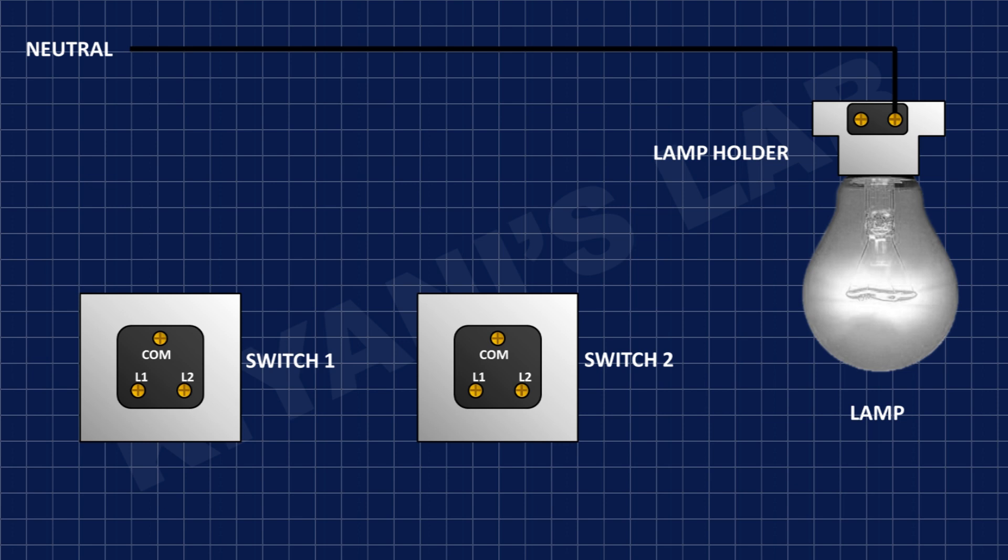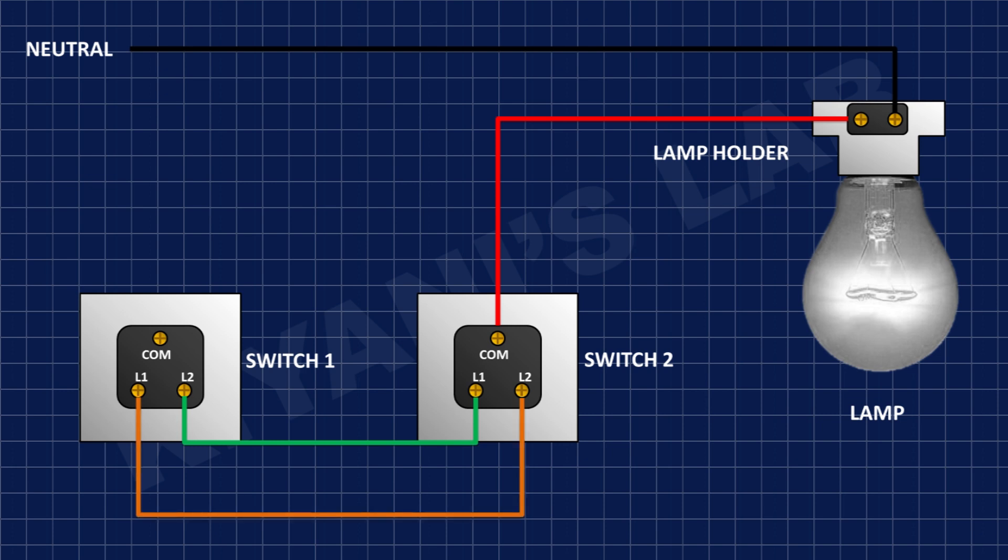After that connect the second wire of lamp holder to common pin of switch 2. After that connect L1 pin of switch 2 to L2 pin of switch 1. After that connect L2 pin of switch 2 to L1 pin of switch 1. After that connect live wire to common pin of switch 1.